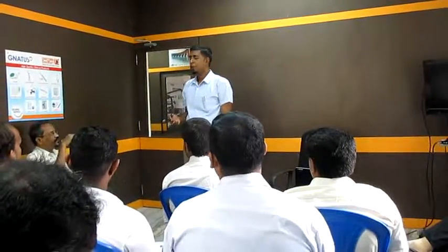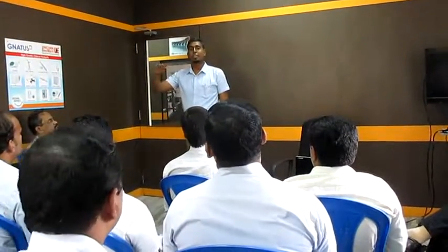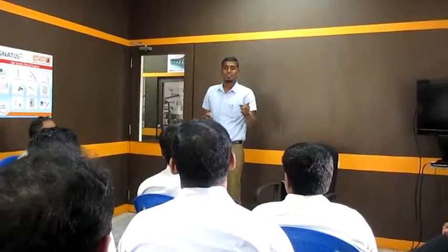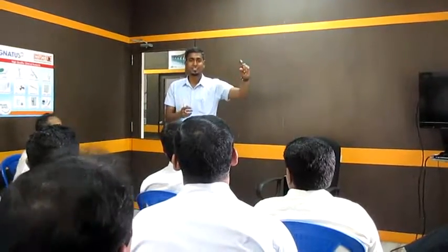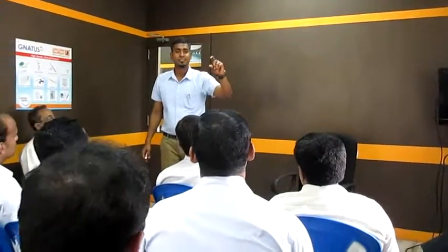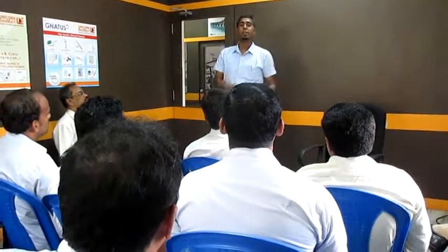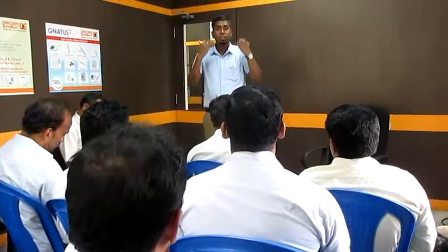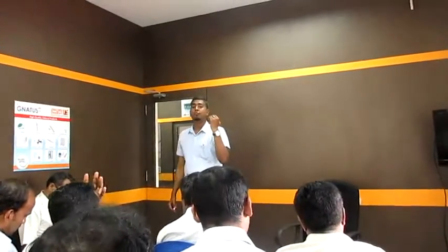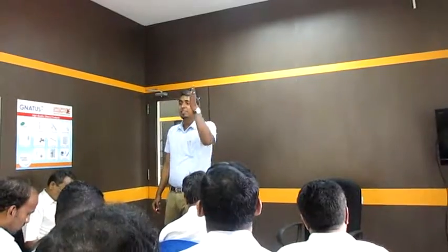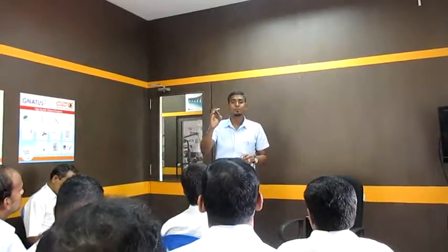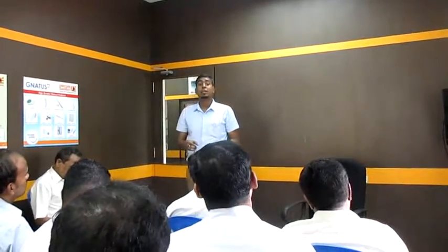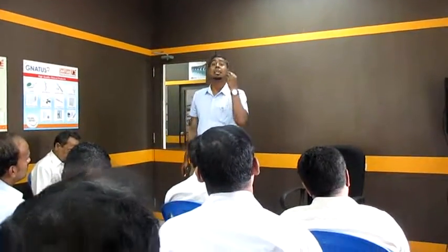If you have a child, if he is your son, he will get certain features of yours. That is inherent features, right? That is inbuilt. So an X-ray machine has certain inbuilt filtration also. That inbuilt filtration is known as inherent filtration. And there is another type of filtration that we add. The aluminum sheet we add in front of the X-ray tube, the aluminum filter, is basically an added filter.